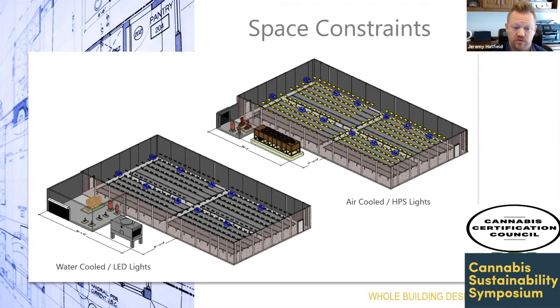If you don't know what system you're going to use when you're laying out the floor plan, you're most likely going to get it wrong. In this particular case, the water-cooled system is going to require a mechanical room size that's 2 to 3 times the size of an air-cooled system.